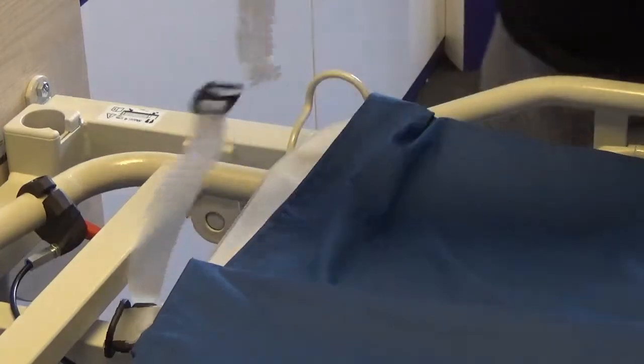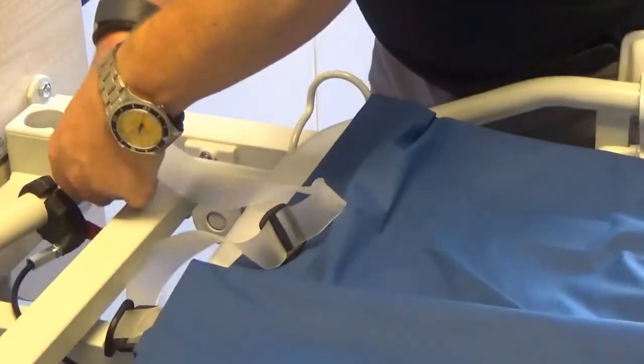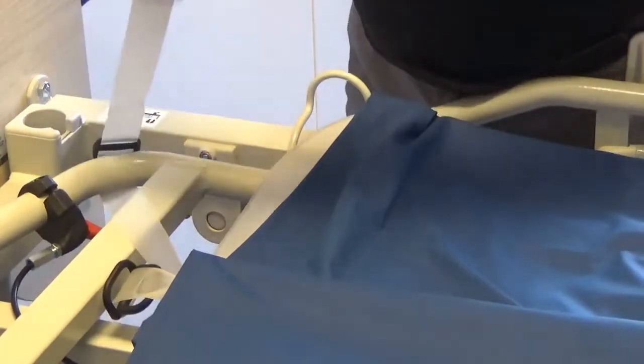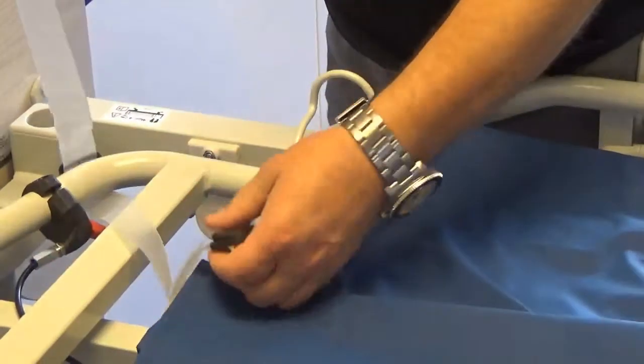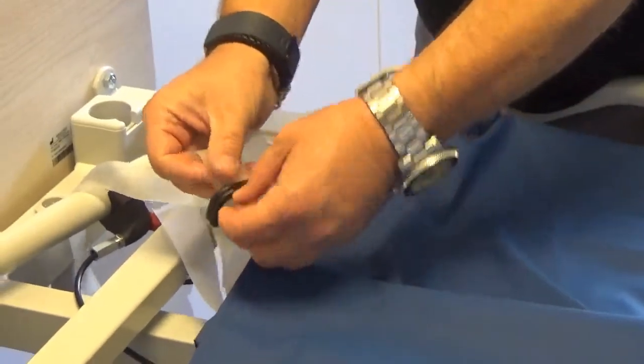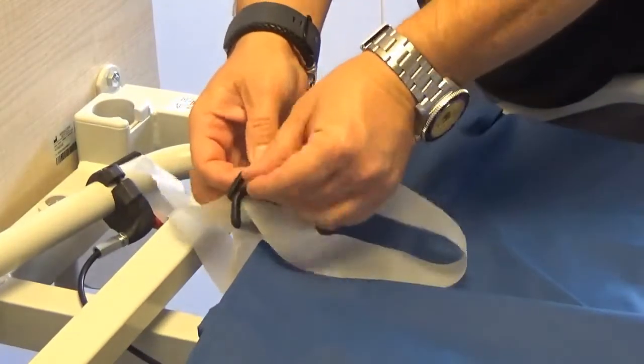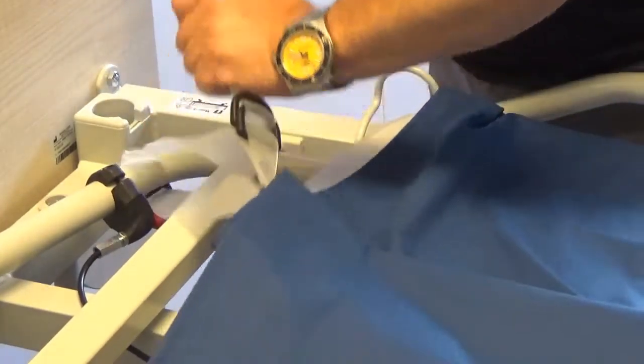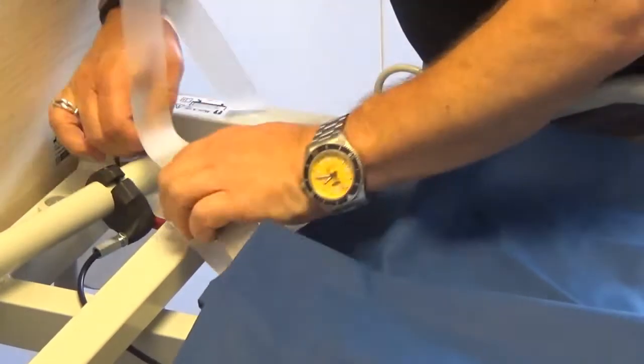To secure the air chamber system to the bed and prevent lateral movement, there are 4 straps that should be used to attach it to the base of the bed. The straps must be attached to the moving parts of the profiling bed and be directed diagonally towards each other. Use the D-rings to secure.